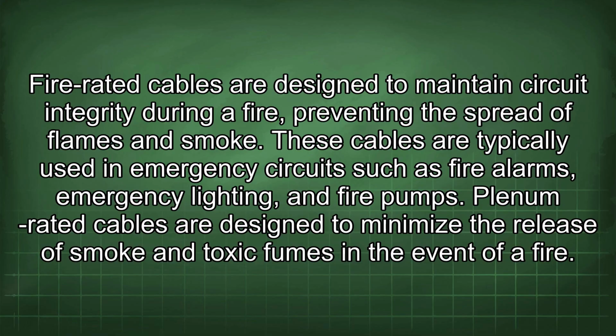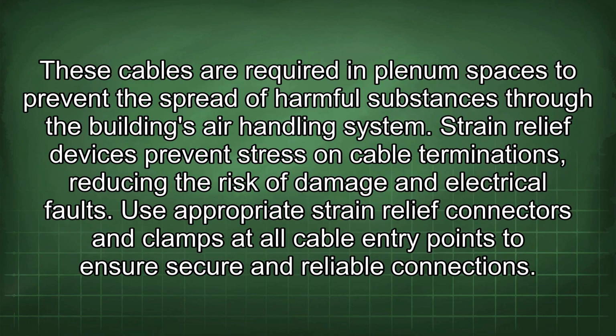Fire-rated cables are designed to maintain circuit integrity during a fire, preventing the spread of flames and smoke. These cables are typically used in emergency circuits such as fire alarms, emergency lighting, and fire pumps. Plenum-rated cables are designed to minimize the release of smoke and toxic fumes in the event of a fire. These cables are required in plenum spaces to prevent the spread of harmful substances through the building's air handling system. Strain relief devices prevent stress on cable terminations, reducing the risk of damage and electrical faults. Use appropriate strain relief connectors and clamps at all cable entry points to ensure secure and reliable connections.